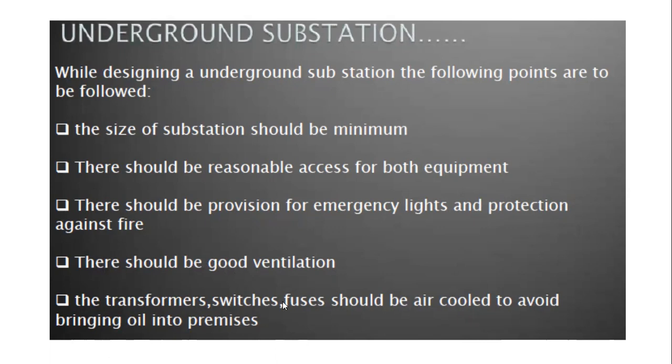Next, the transformers, switches and fuses should be air cooled, to avoid bringing oil into the premises. Leakage of oil can cause sparks. Since this is an underground substation, all the equipment is very near to each other, so faults are quickly obtained. That's why the fuses, switches and transformers should be air cooled, to avoid oil in the premises.